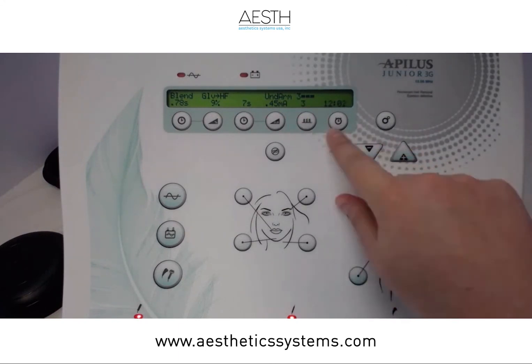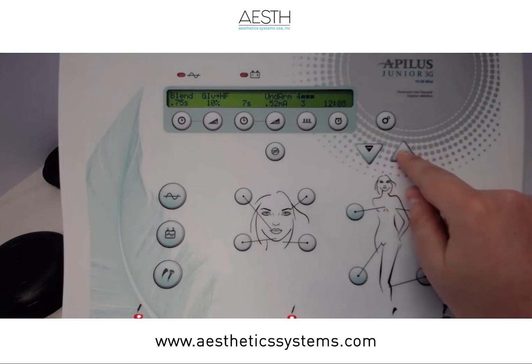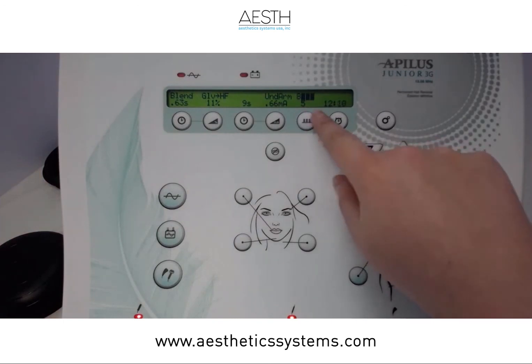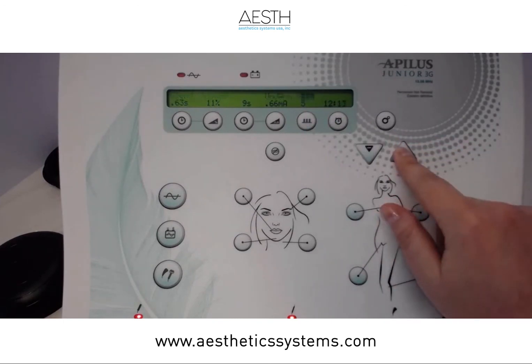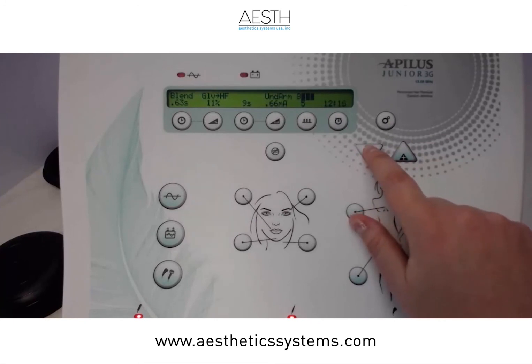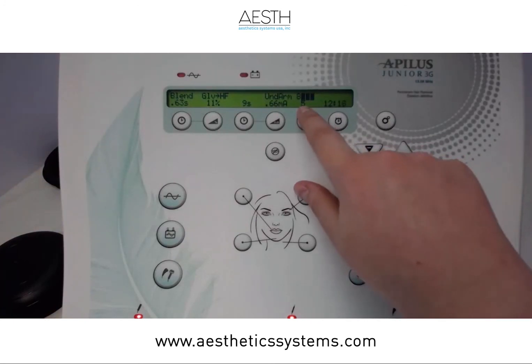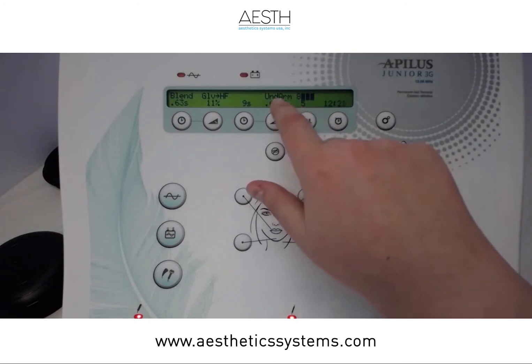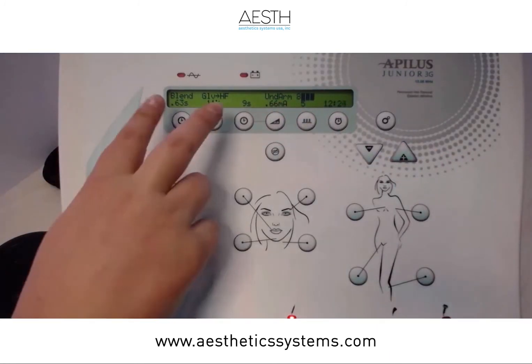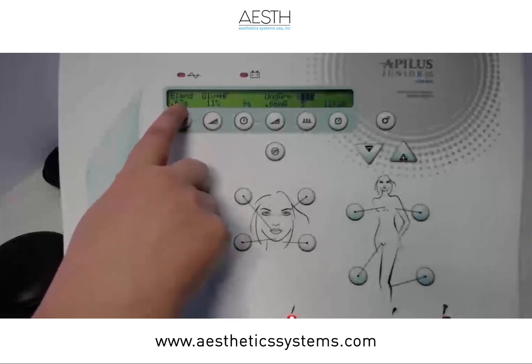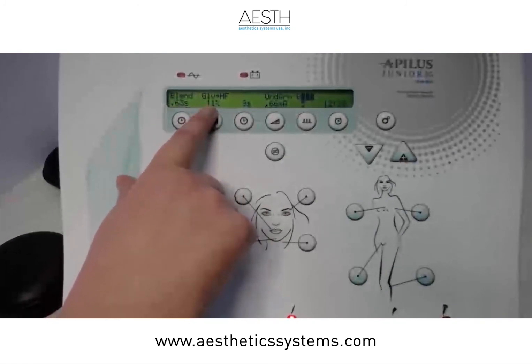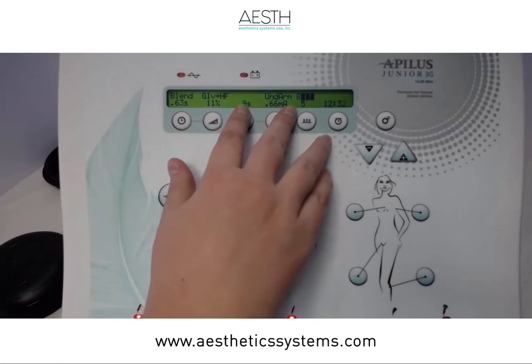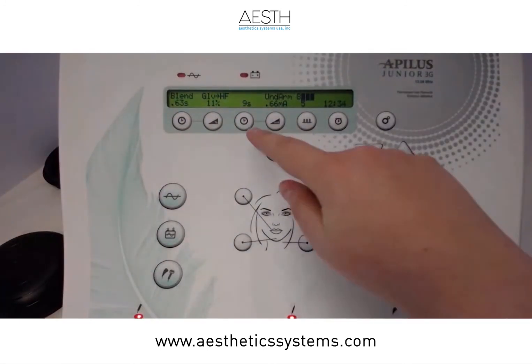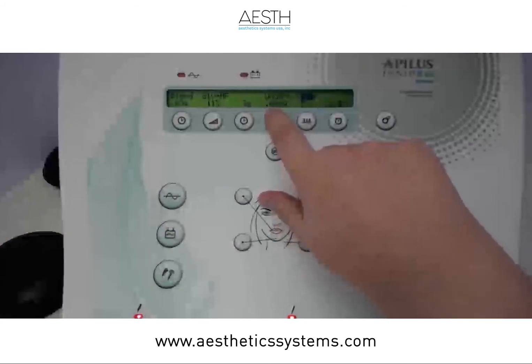The higher the preset, if I go up here, the more these settings will increase, and also the pulses. Now I have 5 pulses. 8 is my highest here, so we can't go much higher than this. This is the highest preset I have on this machine. From left to right, we have the high frequency settings here, 0.63 seconds, 11%. When I see a percent, I know that I'm talking about high frequency. In the middle, we have our galvanic settings. We have a 9-second pulse at 0.66 mA, and there are 5 pulses of high frequency.